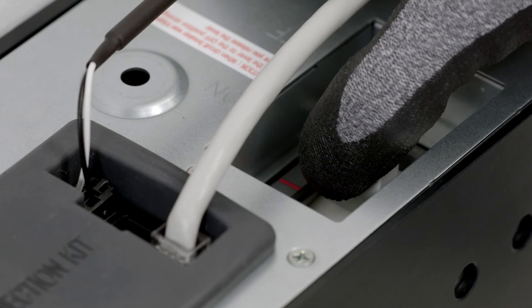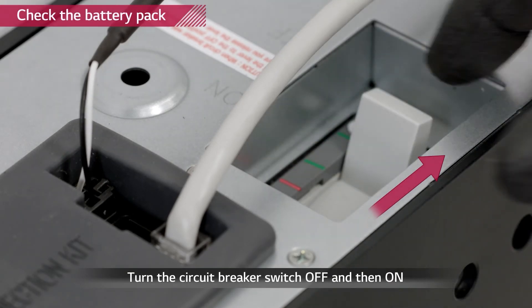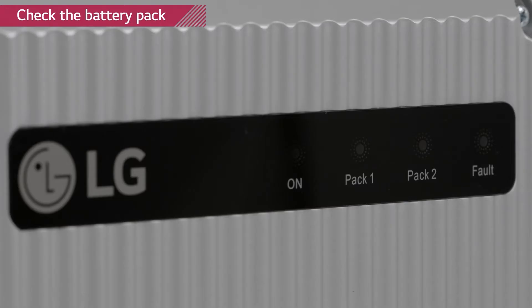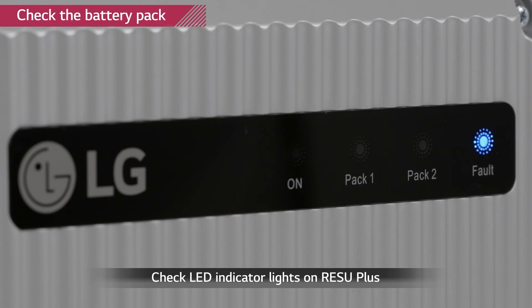Reattach the top cover and tighten the screws with a torque of 1 Nm. Turn on both RESU packs by moving the circuit breaker to the off position first, then to the on position. The three lights at the indicator of the RESU Plus will appear if the installation is performed properly.